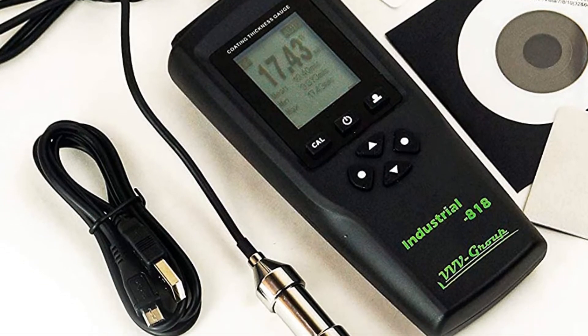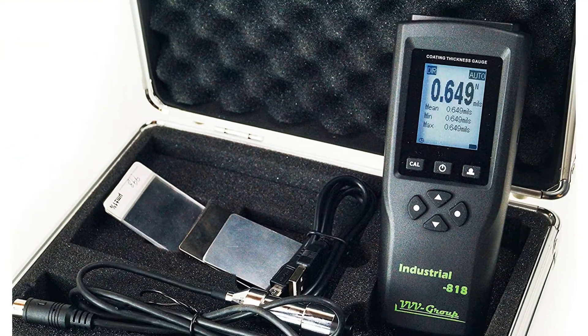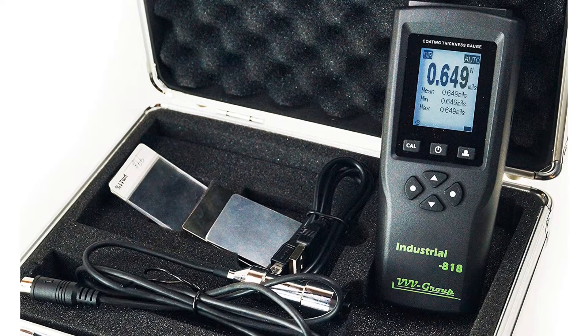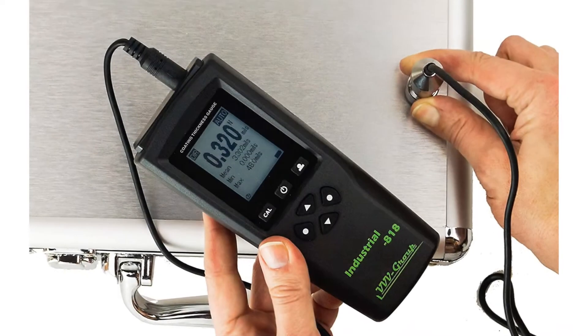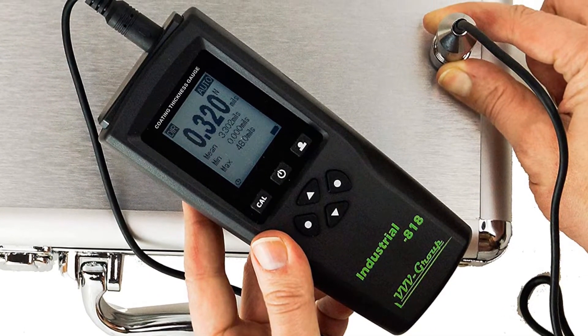It has a measuring range of 0–197 mils (0–5 mm) for magnetic metal surfaces, and 0–118 mils (0–3 mm) for non-magnetic metal surfaces. The digital LCD screen displays the readings clearly, and the user interface is simple to use with three measurement units: mils, microns, and mm.